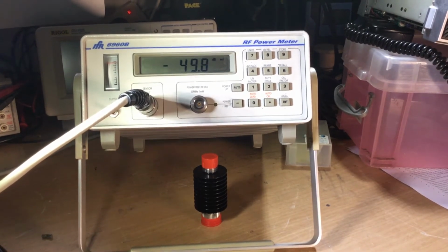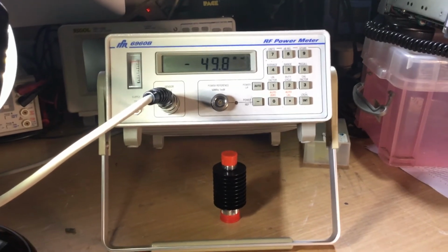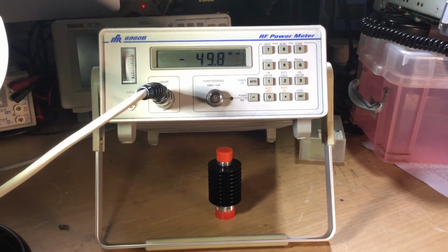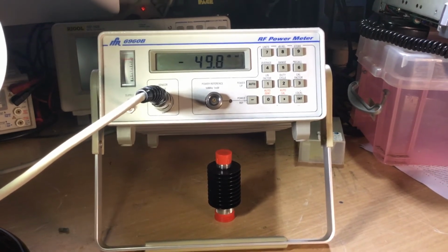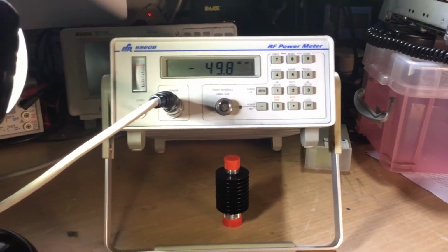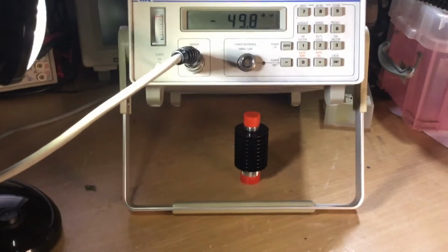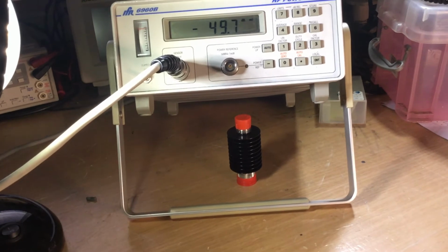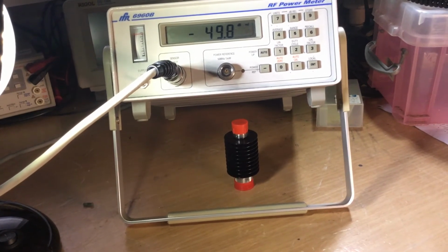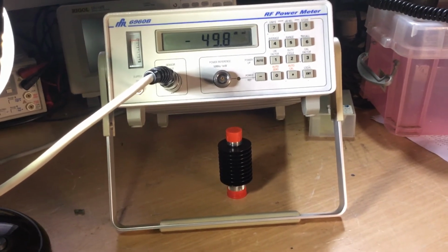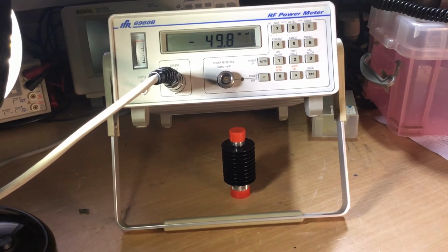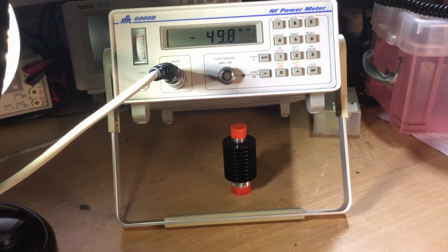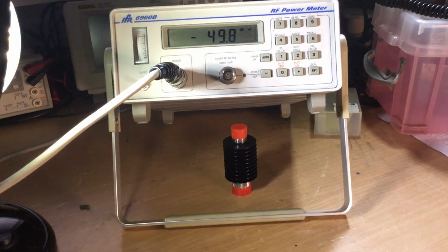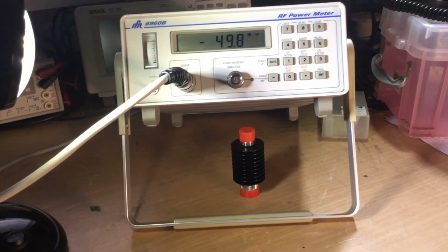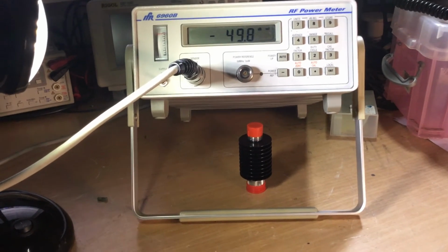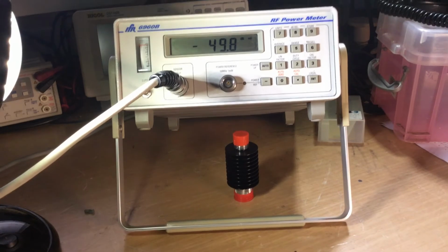So basically it says that for the specification, the frequency range is 30 kHz to 46 GHz depending on the sensor used. The power range is minus 70 dBm to plus 44 dBm depending on the sensor used. The power reference, which is this N-type socket here, gives a 0 dBm, 1 milliwatt output at 50 MHz, on the Type N precision connector, 50 ohm. The uncertainty is plus or minus 0.07%, traceable to national standards. The accuracy is plus or minus 1.2%, worst case for 1 year. It's a 4-digit LCD. The instrument accuracy in watts mode is plus or minus 0.5%. In dBm mode, plus or minus 0.02 dB, and in dB relative mode, it's plus or minus 0.02 dB again.